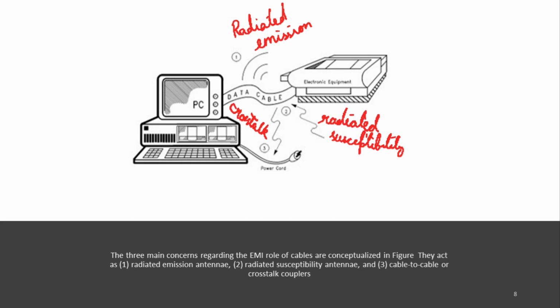Usually, whatever is done to harden a cable against radiated emission will also work in reverse for controlling EMI radiated susceptibility. The reason is that when differential mode radiated emission or susceptibility is the failure mode, twisting leads and shielding cables reduces EMI. If the failure mechanism is due to common mode currents, which we'll be talking about, circulating in the cable, twisting leads has essentially no effect on the relationship between each conductor and the common mode reference. Cable shields may help or aggravate EMI depending upon the value of the transfer impedance of the cable shield. Transfer impedance is a figure of merit of the quality of cable shield performance, defined as the ratio of coupled voltage to surface current on a per meter basis.